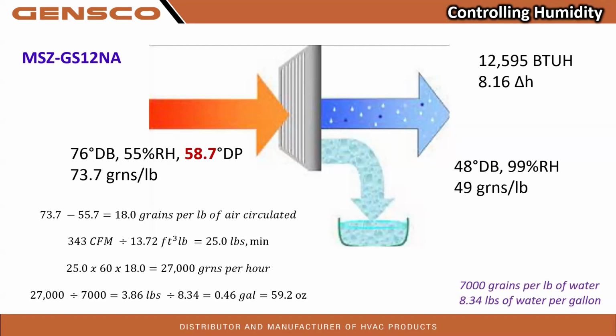And if we multiply that times 60 minutes in an hour, we are removing 27,000 grains per hour. Divided by 7,000 is 3.86 pounds, divided by 8.34 times 128. We are removing approximately 0.46 gallons or 59 ounces of water, physical water, if this unit ran for 1 hour. Let that sink in. 1 hour of running, we could remove 60 ounces of physical water. Pretty good, but we have to run. To run, we need a load.